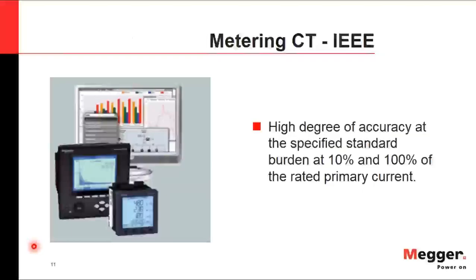For metering-type CTs according to IEEE, there is a high degree of accuracy at the specified standard burden at 10% and 100% of rated primary current. What we are looking at is a very specific and accurate measurement of current, and the transformation from primary to secondary has to be extremely accurate.